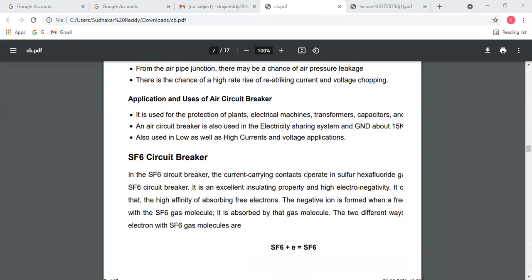Now, coming to the next breaker, the SF6 circuit breaker. In the SF6 circuit breaker, the current carrying contacts operate in sulfur hexafluoride gas. It has excellent insulating properties and high electronegativity. It has a high affinity for absorbing free electrons. A negative ion is formed when a free electron meets an SF6 gas molecule and is absorbed by the molecule.